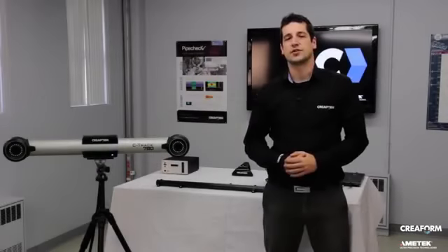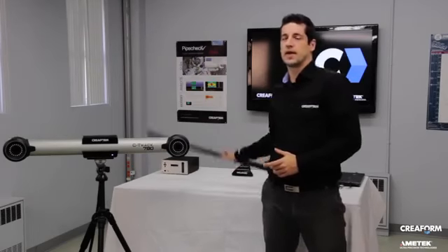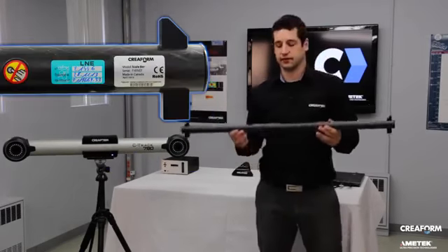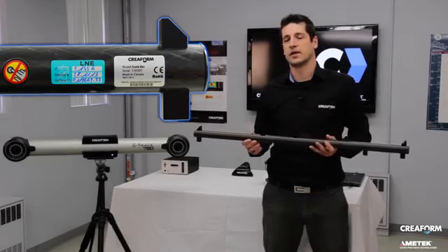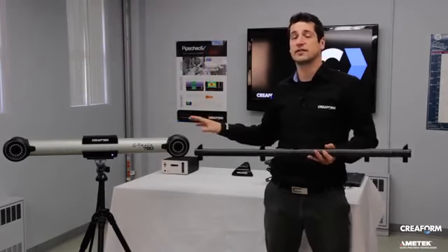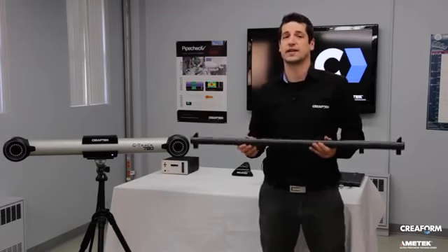The calibration of the C-track is done using the calibration bar. As mentioned earlier, this bar is a traceable certified artifact. So the calibration is done to check the system against a known standard to make sure that it is accurate.